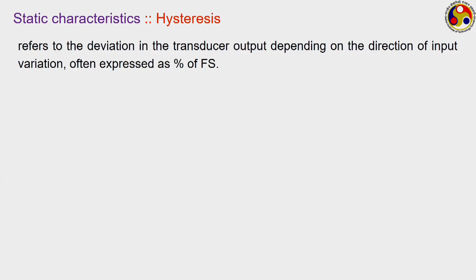Certain instruments may show hysteresis behavior, where the output depends on the direction of change in input. Moving in the forward direction for a particular input gives one output, but coming back for the same input may give a different output. If there's a negative slope while coming back, you get yet a third output for the same input. Certain instruments show hysteresis depending on friction, elastic deformation, wear and tear, or aging problems. Again, repeated calibration can help solve the hysteresis problem.